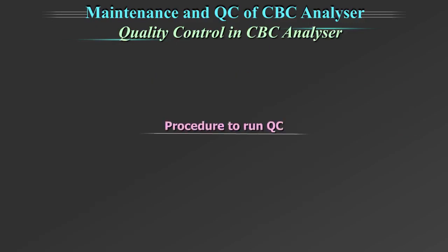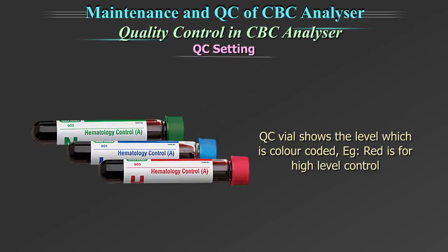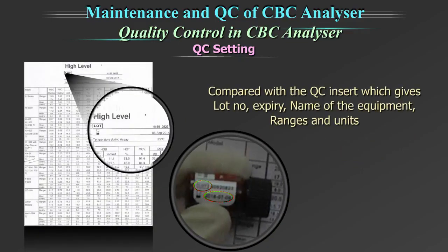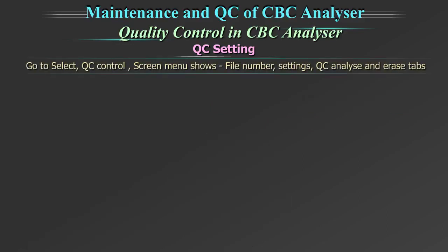Procedure to run the quality control. We will show you a sample quality control procedure using this equipment. It could be different on yours and has to be understood from your equipment manufacturer. Start with QC setting. The QC vial shows the level, which is color coded. For example, red is for high level control. Note the lot number and date of expiry.